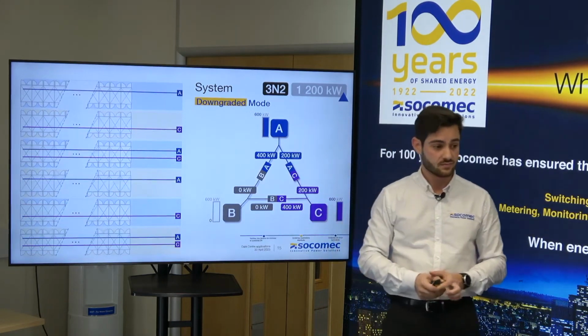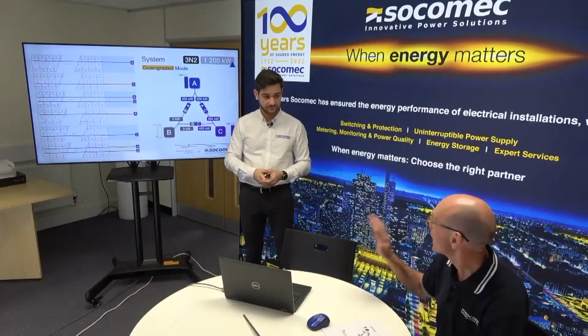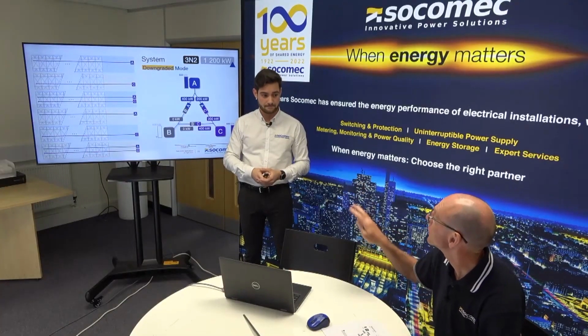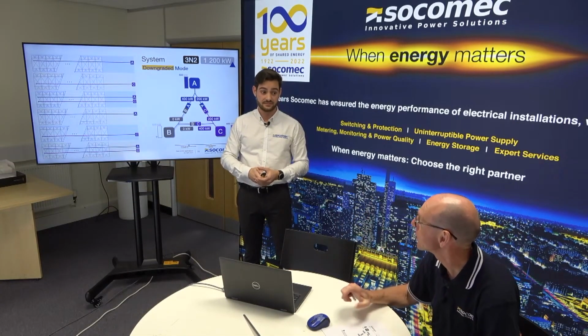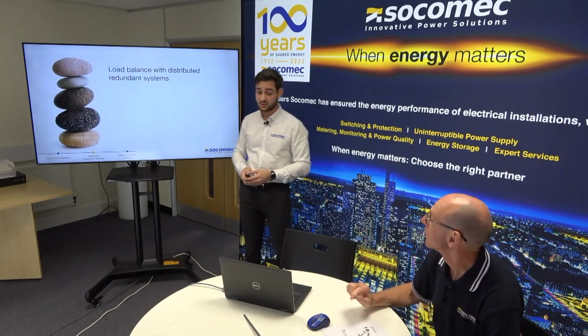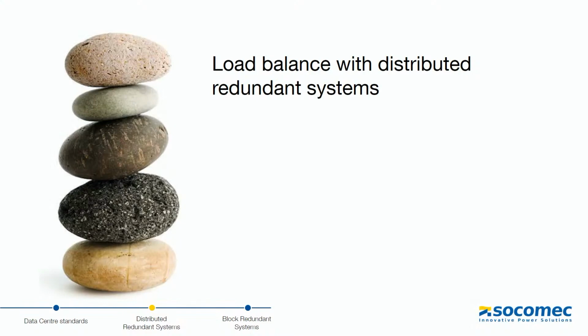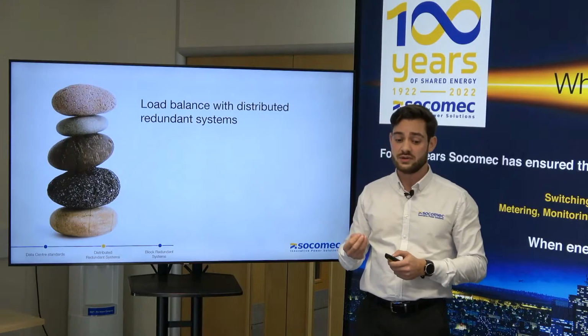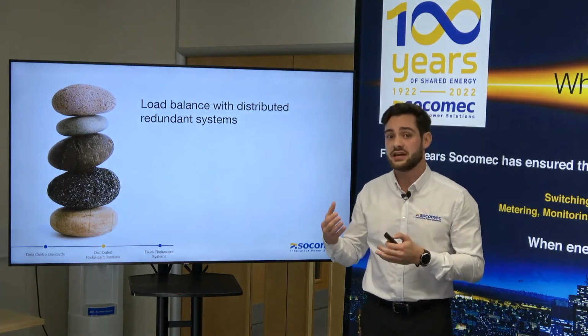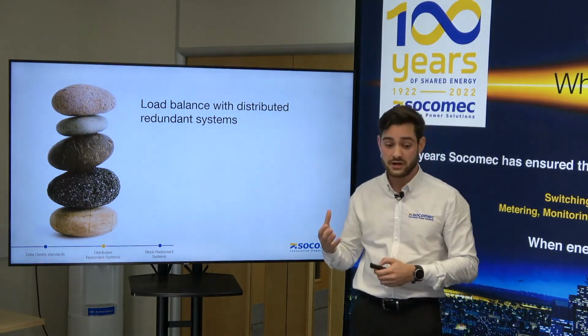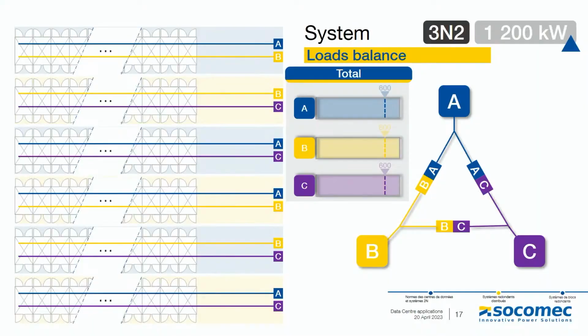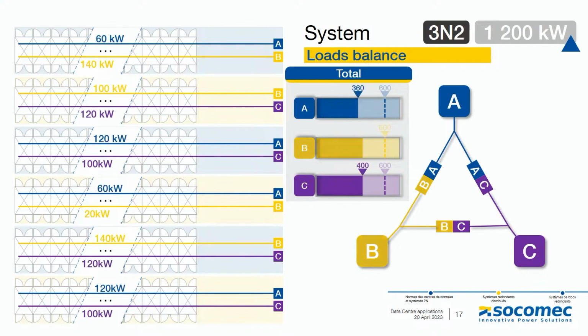But obviously what's important there is that you have the load balanced correctly across those 3 UPSs, as I think you're going to show. Very important to understand this. So, load balance with distributed redundant systems. It's really a key point and really something that needs to be understood because it can have a lot of implications if it's not done properly. So as Richard said, you've got 3 systems, again 1200 kilowatts load, so you've got the load shared across 3 different systems.